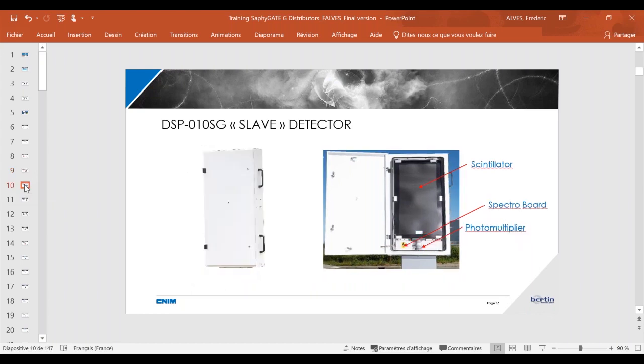Here is a view of the slave detector. Now you know it perfectly. This detector is the same as a master detector, but on the master detector you have the infrared cells and the mixing card. Here you only have the scintillator, photomultiplier, and the spectro board.